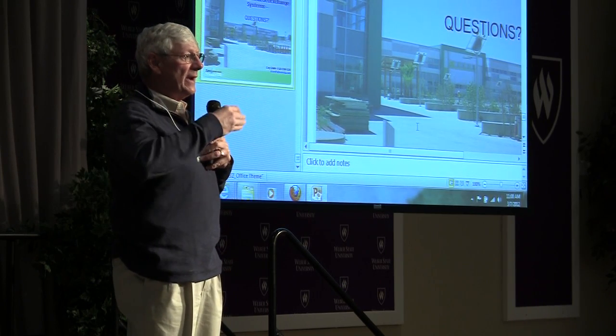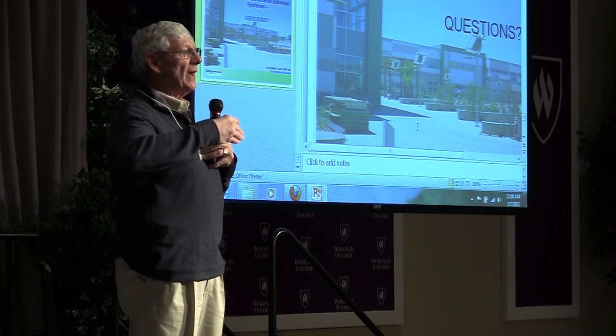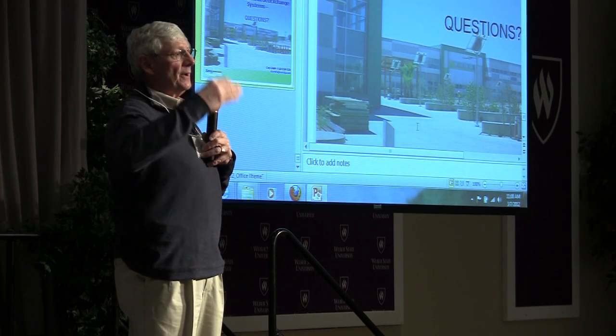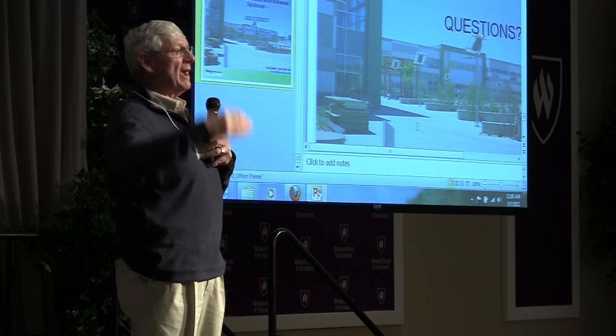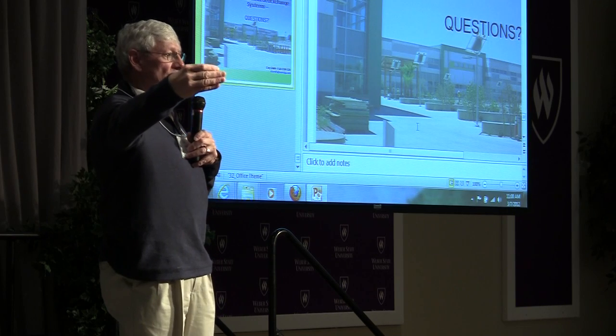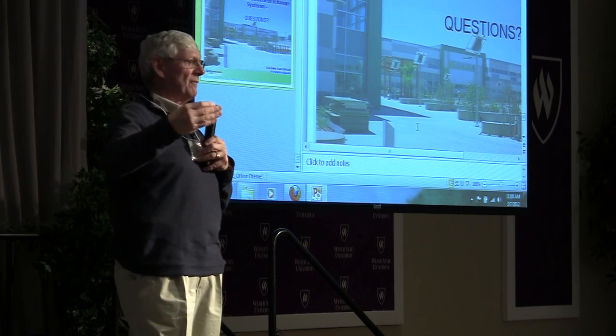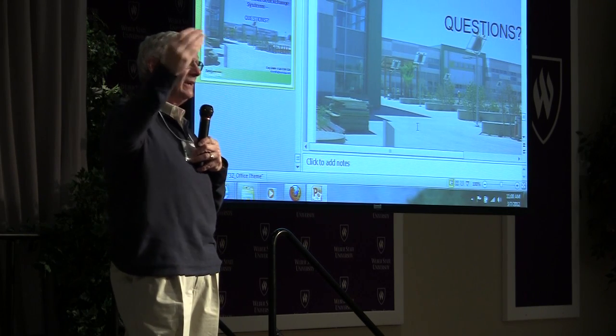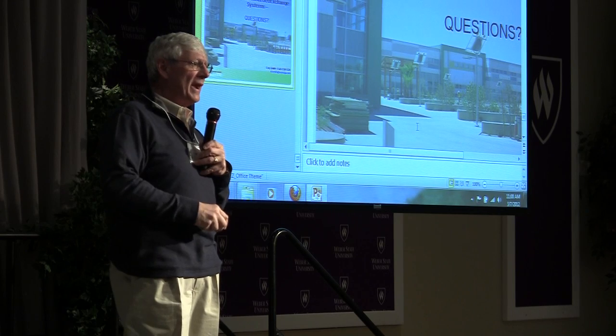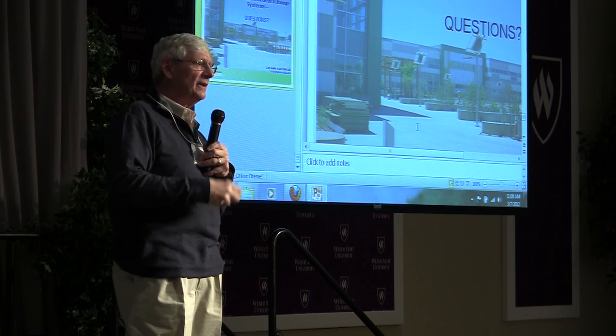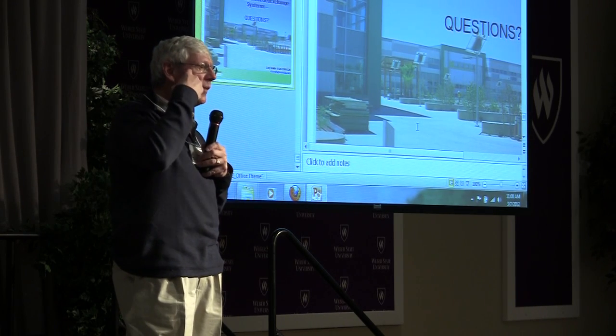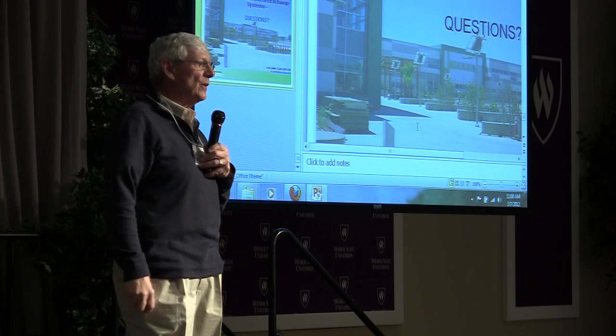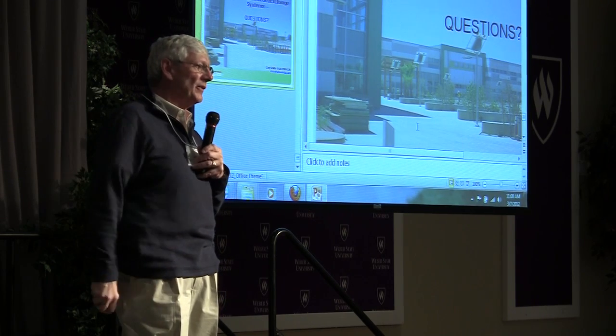Again, that's the limiting factor. We have heat pumps now called extended range units - they're good from entering fluid temperature of 25 to 110. The old heat pumps choked at about 55 entering on the cooling side, and somewhere around 85 or 90 on the heating side - they'd lock up and lose compressors. So the new equipment and design is helping a lot with that.